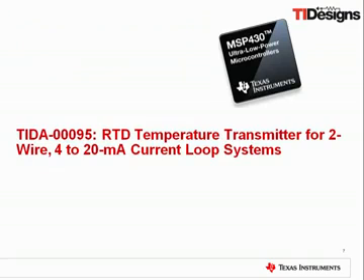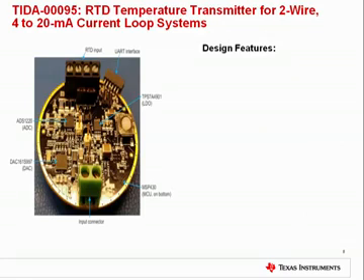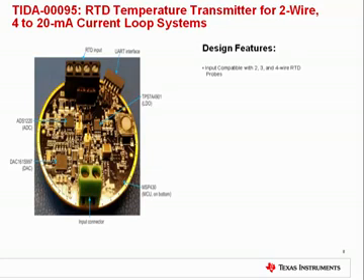The first TI design we will talk about is the RTD temperature transmitter for two-wire, 4 to 20 milliamp current loop systems. This comprehensive design provides a complete system that measures and processes temperature signal inputs from 2-wire, 3-wire, and 4-wire resistance temperature detectors and outputs a 4 to 20 milliamp current loop signal corresponding to the processed temperature. The reference design is intended for process measurement applications in factory automation, field transmitters, and building automation, due to its low power consumption.